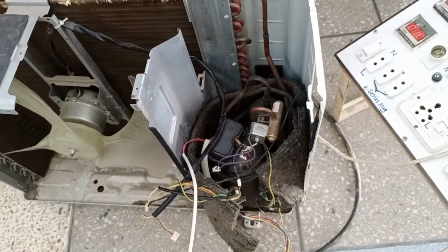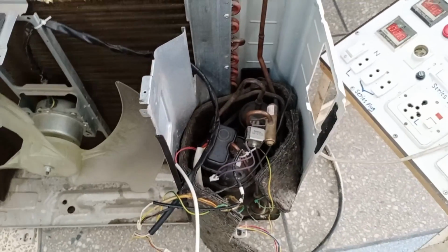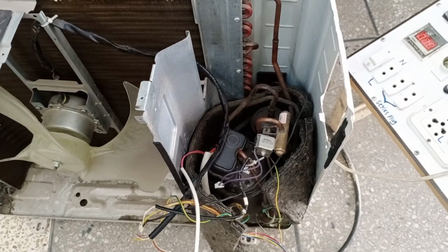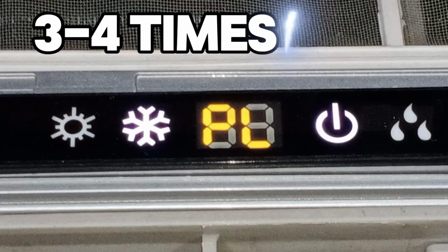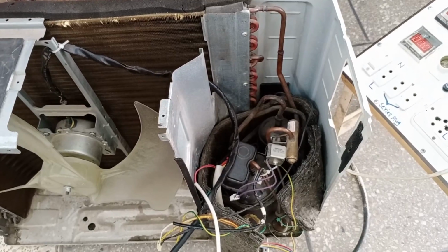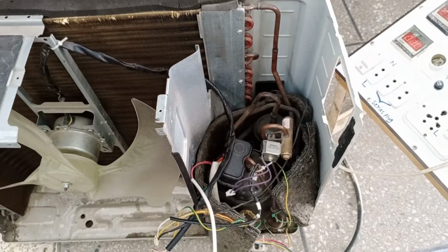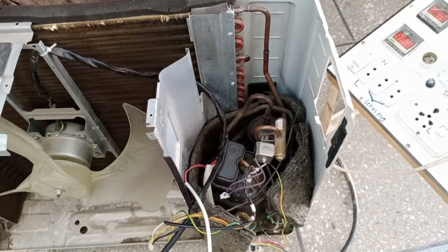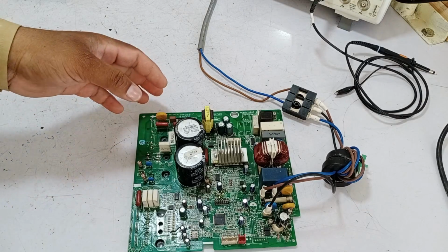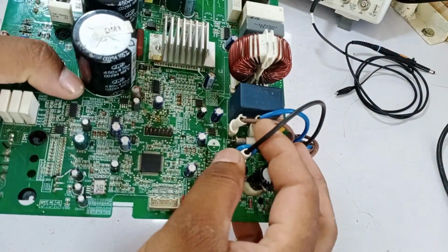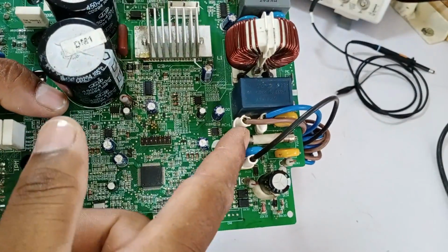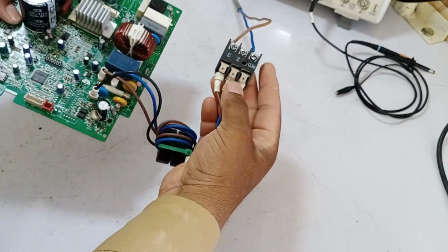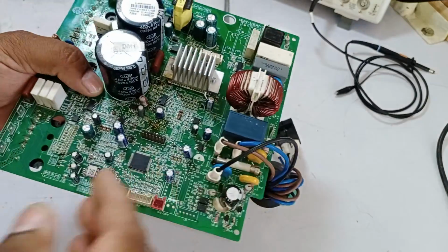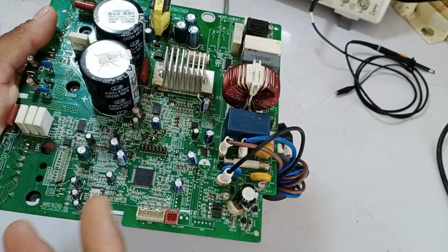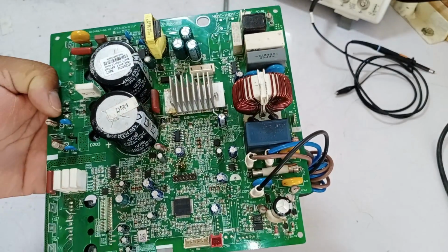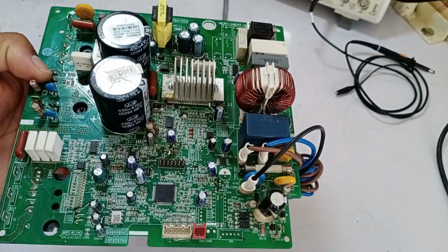The third situation could be this: you supplied power to your unit. This time, the compressor also started, but the AC is showing PL 3 to 4 times in 1 hour. If the unit starts and stops and shows PL, then the circuit board could be the reason for this error code. Let me tell you what could be wrong with the circuit board if PL is displayed. The reason could be the loose connection on the main supply of the circuit board. Other than this, if the loose connection is on the main power connector of the circuit board, when the current flows through these, it will spark, which will break the flow of current. The PL error code will be shown on the air conditioner's display.